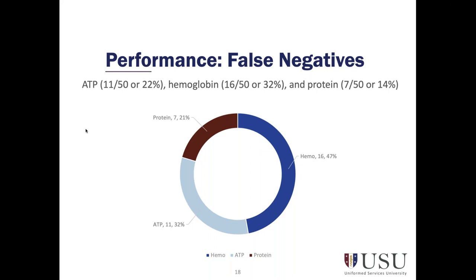So all the systems have their limitations. What I want you to do is make sure that the staff and employees know that when that happens, they cannot take a false negative as a true negative and then push the instrument to be packed. If you swab that instrument and any system gives you a negative read, but you see visible content on that cotton swab, send that instrument back and get it recleaned. You don't know what that is in there. Or if you have any other system available, test it with that system. Otherwise, send it back, get as much as you can out of there. It could be rust, it could be the instrument decaying, but you don't know that at that point. So you need to make sure that the instrument is as clean as possible before you push it to prep and pack.